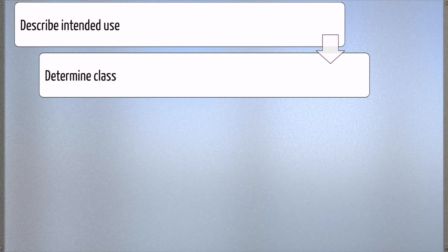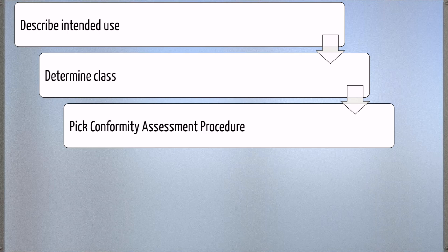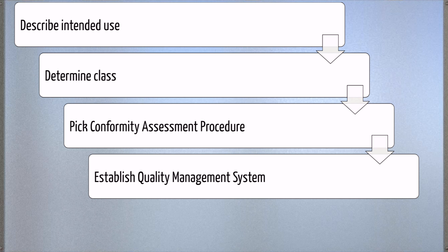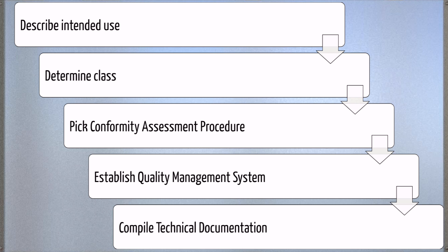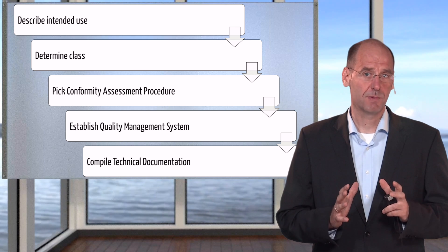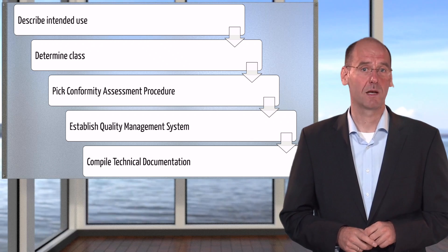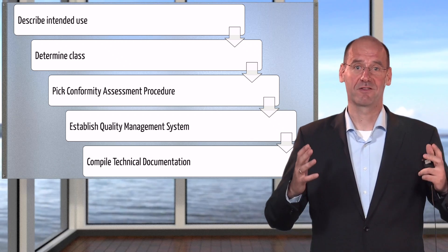The typical steps to market your medical device in Europe are the following. First, describe the medical purpose and intended use of your device. Second, based on this, determine the class of your device. Third, pick a conformity assessment procedure that suits this class. Fourth, if the class is not class 1, establish a quality management system and have a notified body auditing and certifying it. Then, regardless of the class, compile the technical documentation compliant with the respective harmonized standards or common specifications. You also need a post-market surveillance and vigilance system.